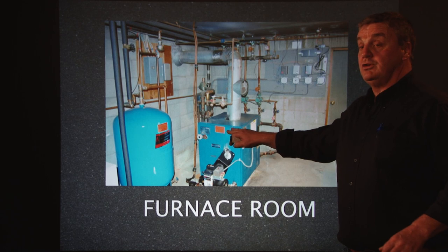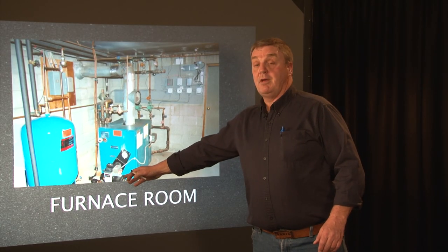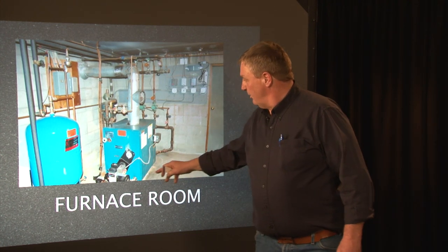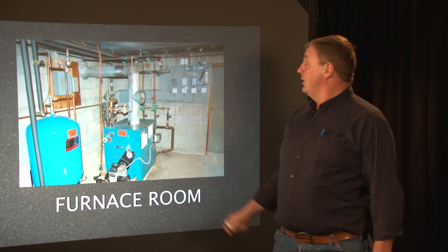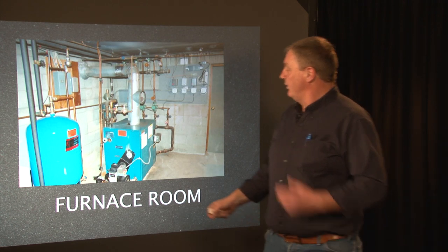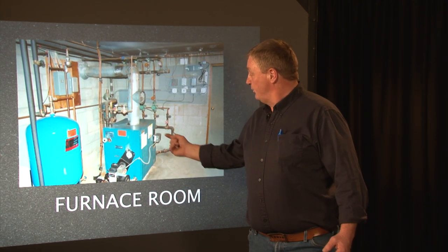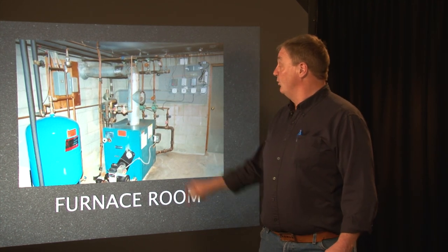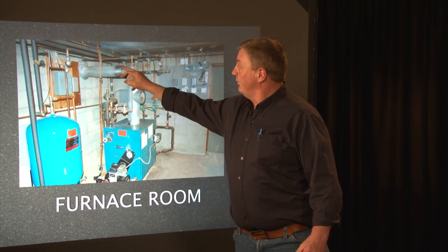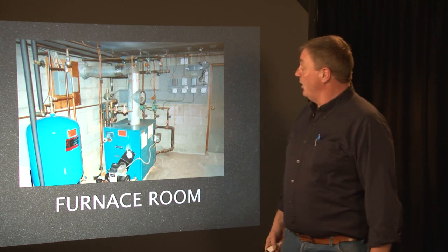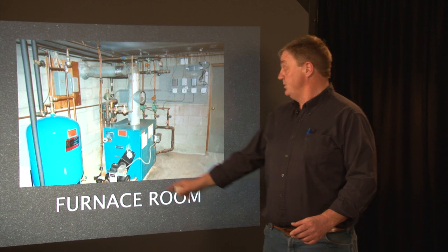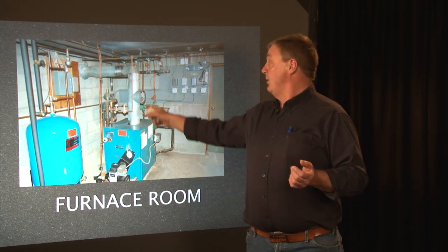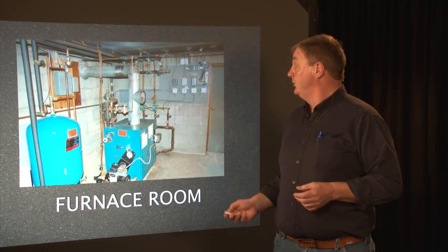There's a furnace room — this is much more like the type of furnace you'll come across in smaller properties. There's a fan motor, a vent going out, the flue taking out the exhaust, and a valve. It heats water; you've got a water system coming through there. You have an electrical control circuit; these panels will come off but you may not want to take them off. Your third-party inspector will decide whether they need to come off — he'll probably look inside the top to make sure the flue isn't restricted, connections are good, and pipe work is good. You'll get a strong smell of oil or gas if it's not mixing and burning properly, so if you're in the room and you smell that, you know you're not getting a good burn.